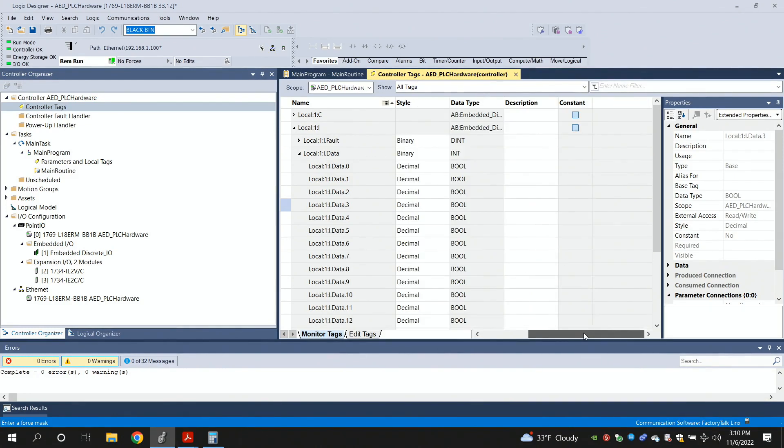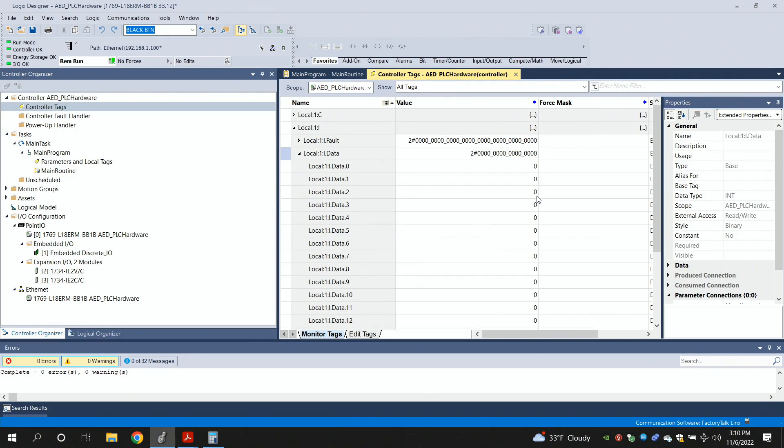The same thing is actually happening inside here. There's 16 bits in this input 1 data. They represent an integer data type. And each one of those represents an individual input on the PLC. I'm toggling those things on and off. So, again, that's all well and good. And it's kind of a useful troubleshooting tool to be able to see this.